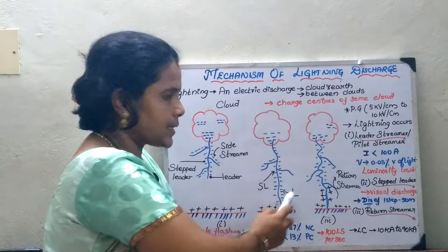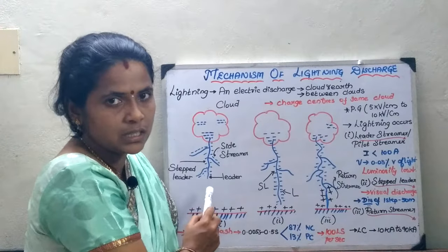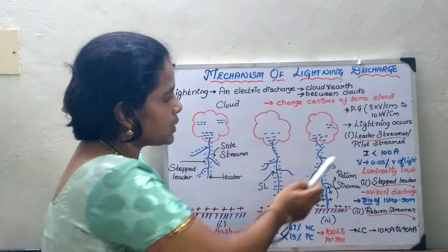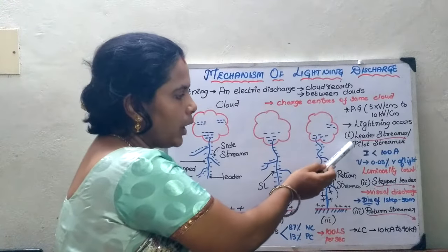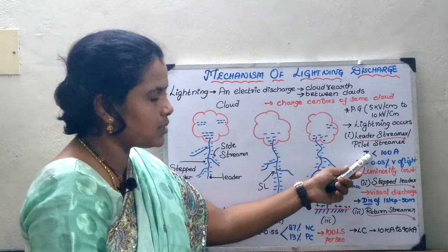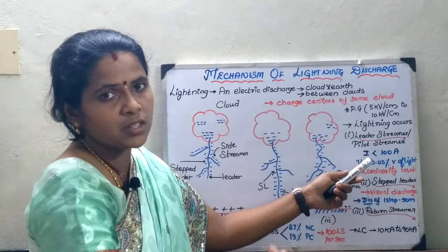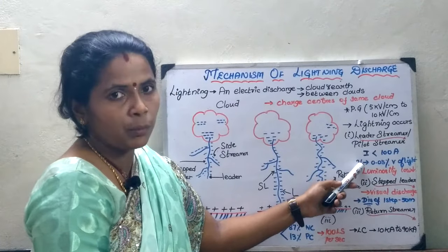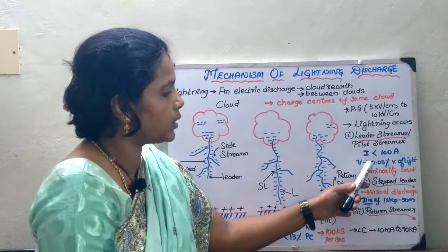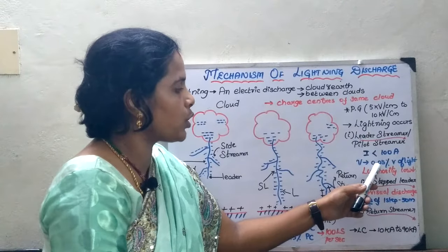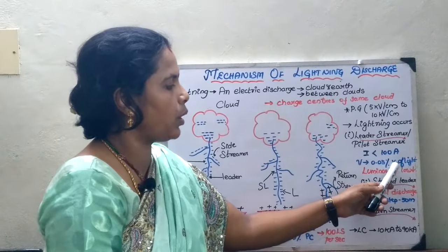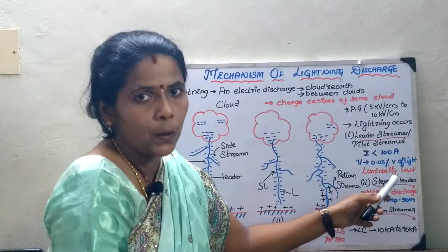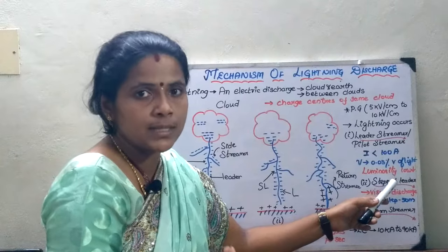In the first case, the luminous velocity of the waveform is very low. There is a leader or pilot streamer and the current magnitude is less than 100 amps, since it does not have sufficient energy to penetrate to the ground. The velocity of propagation is approximately 0.05% of the velocity of light.